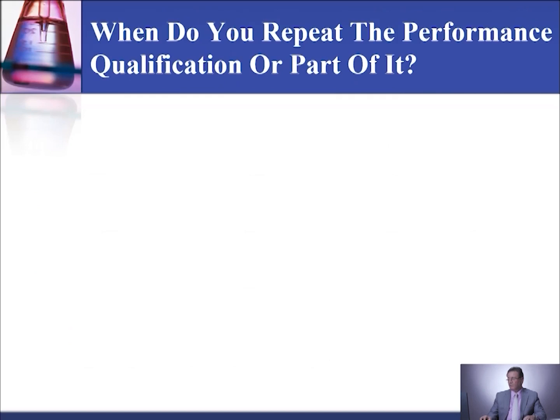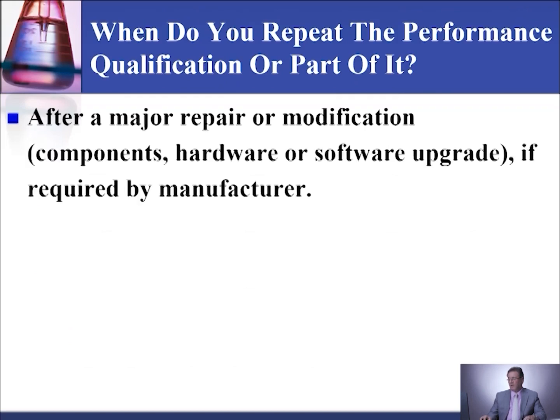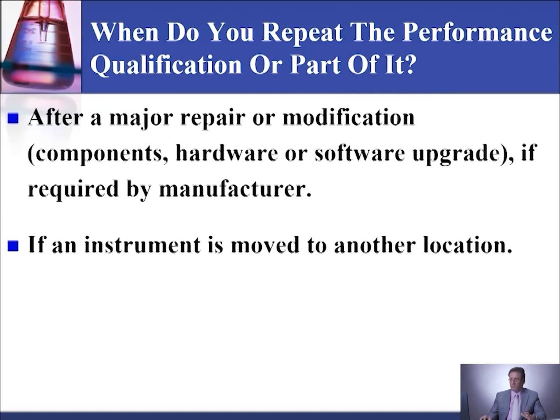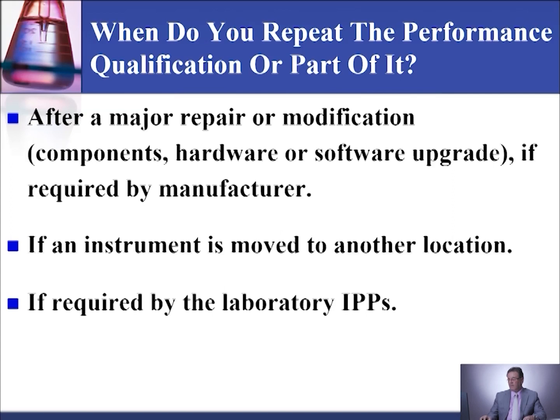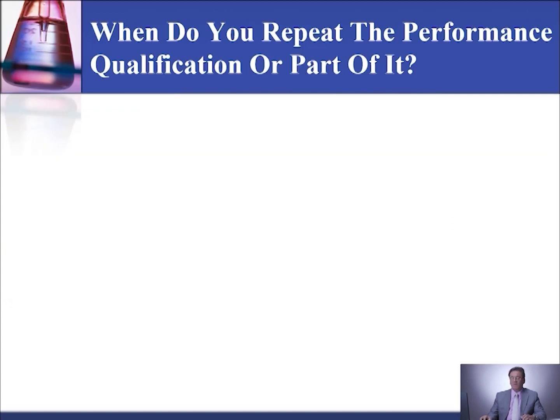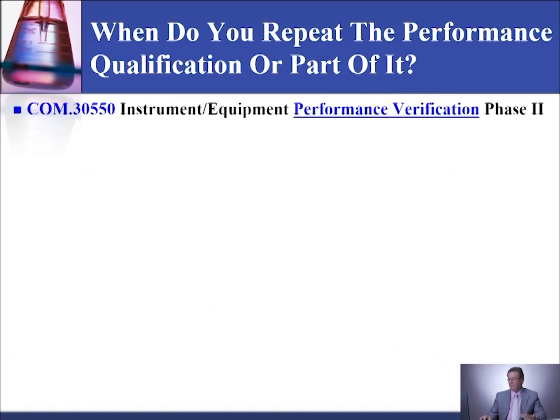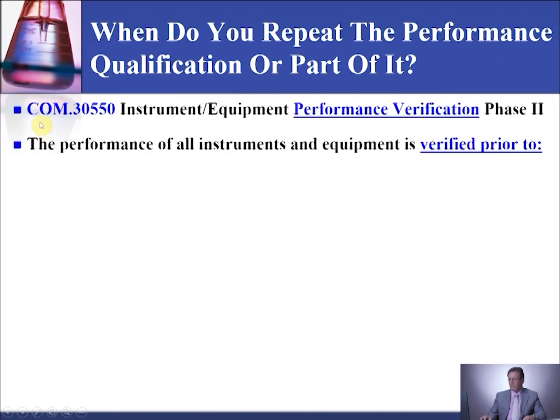When do you repeat the performance qualification or part of it? After a major repair or modification, if required by the manufacturer. So if they replace a part and the engineer tells you that you need to do the performance qualification, then you need to do it again or part of it. Or if an instrument is moved to another location, if required by the laboratory or AABB. When do you repeat the performance qualification or part of it?